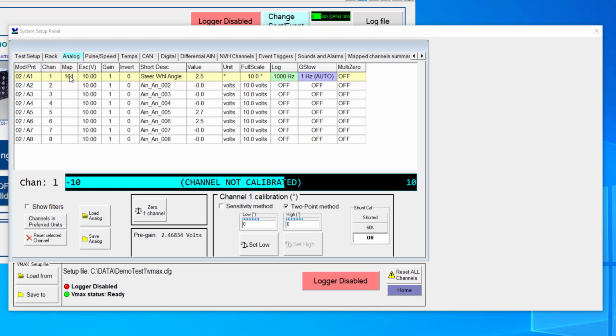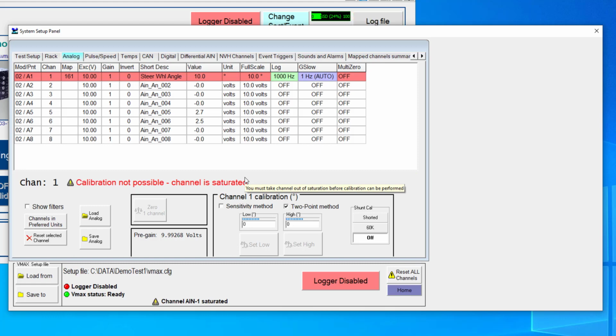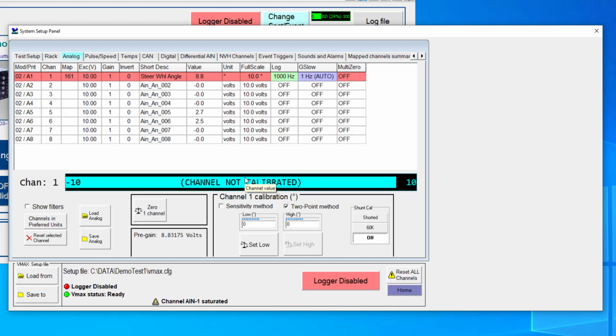So you'll notice once I map this channel, it will actually turn itself on for logging. It will define the unit class. So in this case, the unit class would be angular position, and if I right-click here, you can see that I could change to any other unit that resides in that same unit class. Right now, I am supplying this sensor 10 volts excitation, which I can show you real quickly if we look at the bottom bar on the screen here, which represents the actual raw voltage coming in. If I turn the steering wheel all the way to one direction, it will actually clip. It will actually go to 10 volts, which will saturate the channel.